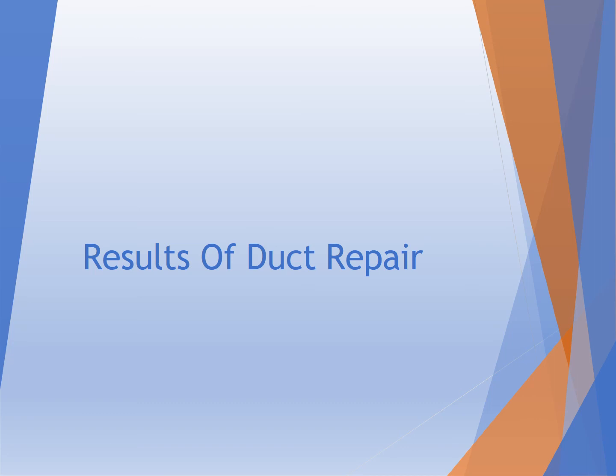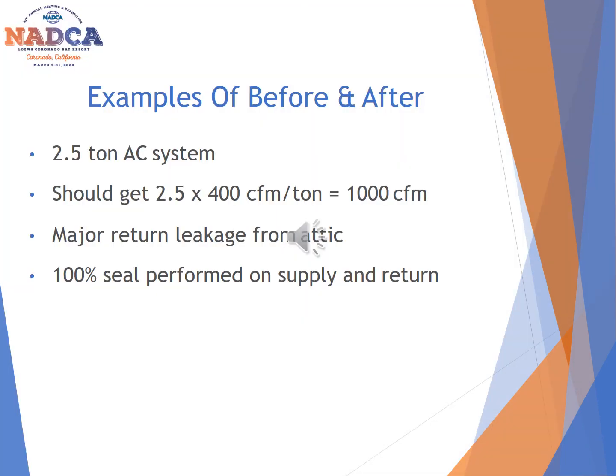Now that we've talked about duct leakage and how it works, let's take a look at some real-life examples and what the end results were with those repairs. So let's take a look at this example. In this particular situation, we have a 2.5 ton AC system. And if you make the assumption that you can get about 400 CFM per ton, then the system should be able to push right around 1,000 CFM. So in this scenario, we have major leaks in the attic. And what they did is they went through and completely sealed the system 100% on both the supply and the return side of it.